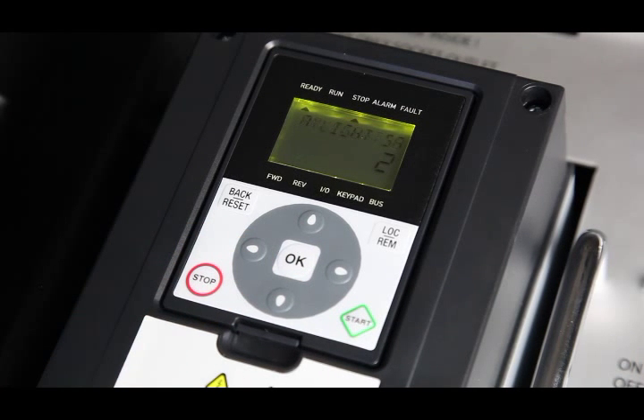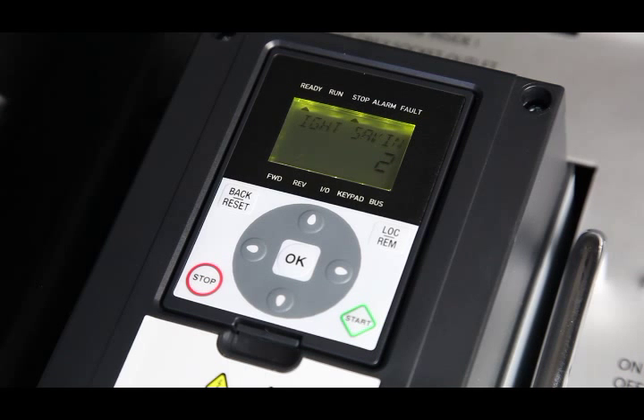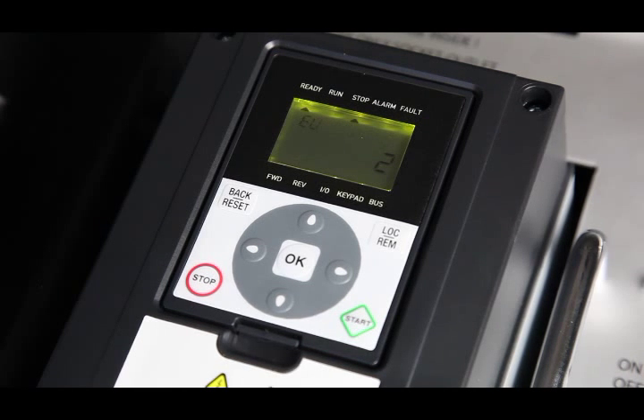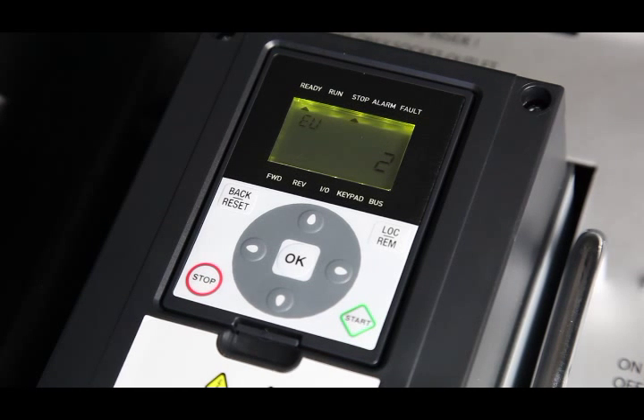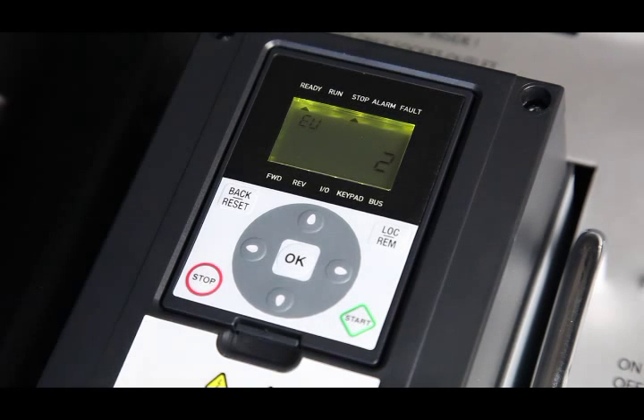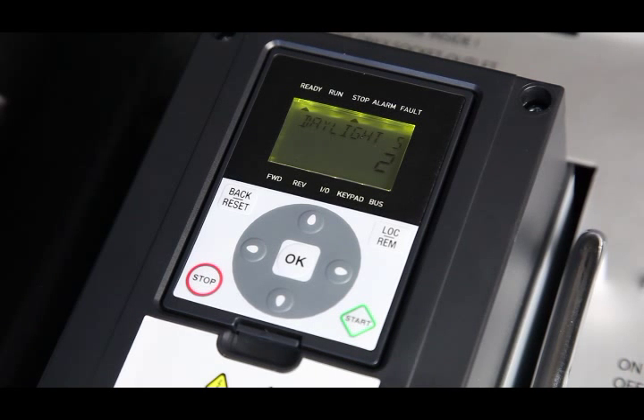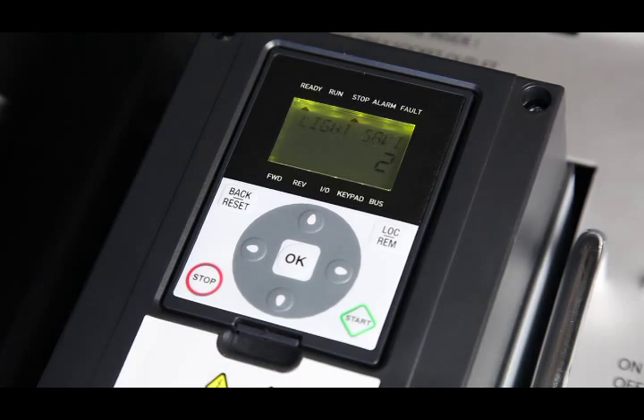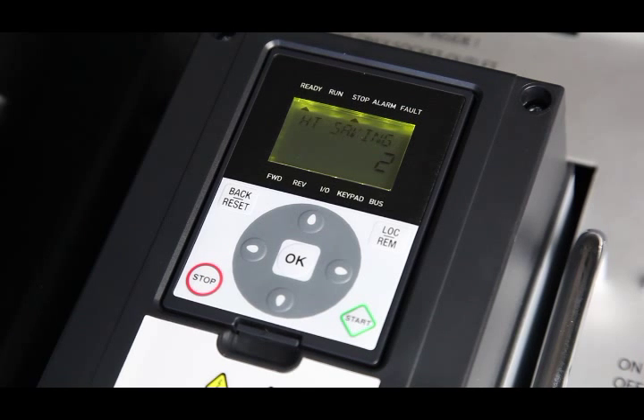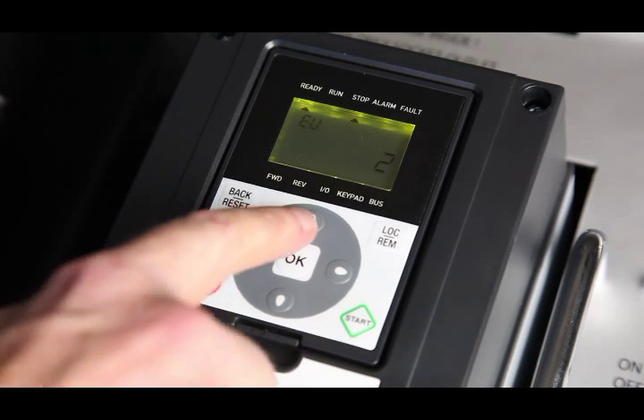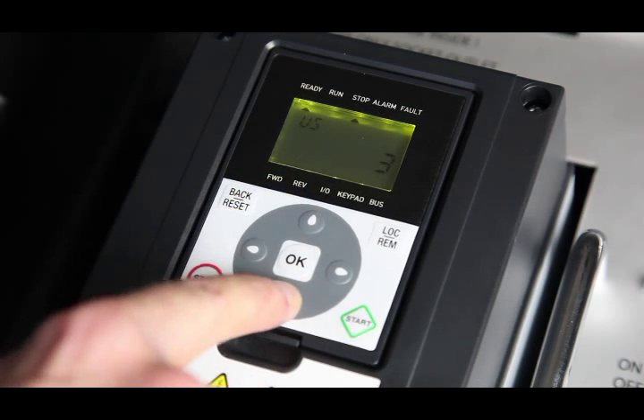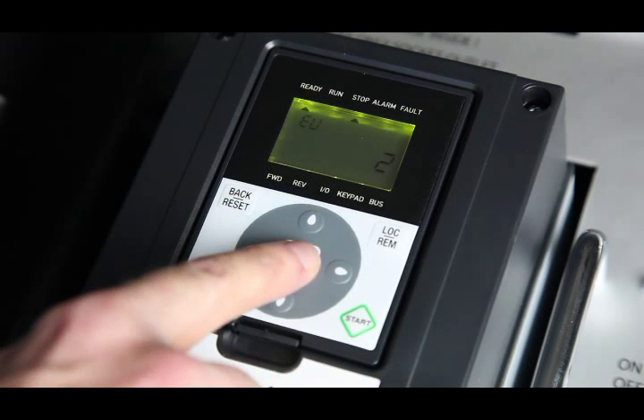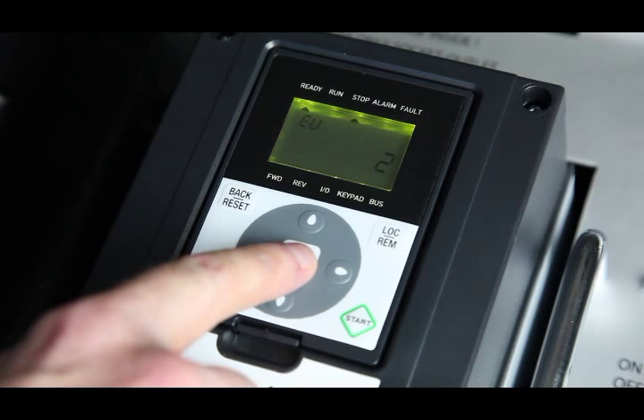The display now prompts for daylight saving. This is necessary as the VSD has an on-board real-time clock which allows the drive to be programmed to perform time-based functions. For UK operation, the parameter needs to be set to EU. Once EU is displayed with the up-down cursor keys, the OK button is pressed.